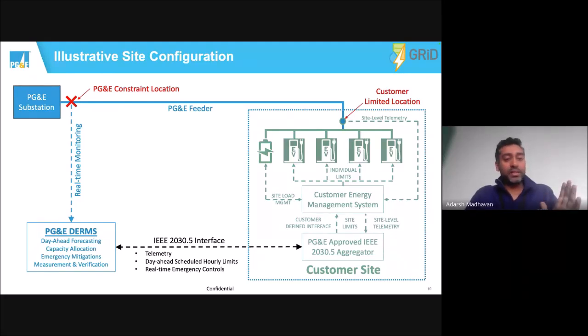So PG&E's DERM system does day-ahead forecasting. It looks at the measurements of all the other customers on the feeder to come up with a forecast of how much capacity will be available for this flexible service connection tomorrow. Using the IEEE 2030.5 interface, we send out 24 values. At 8 a.m. today, we send out 24 values for tomorrow—from 8 a.m. tomorrow to 8 a.m. the day after—giving you the dynamic operating envelope.